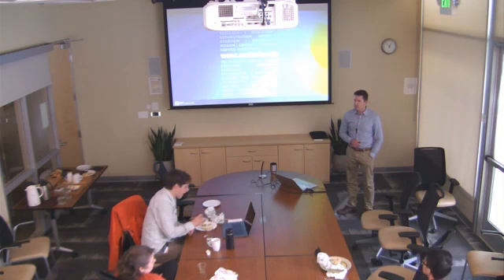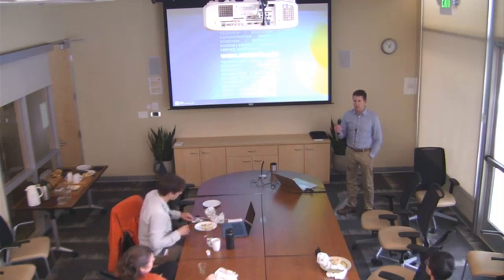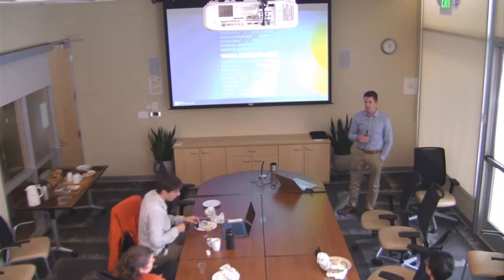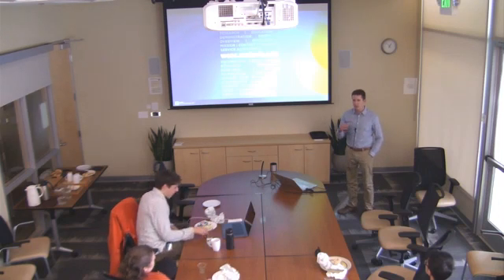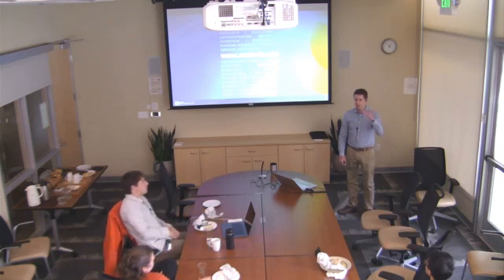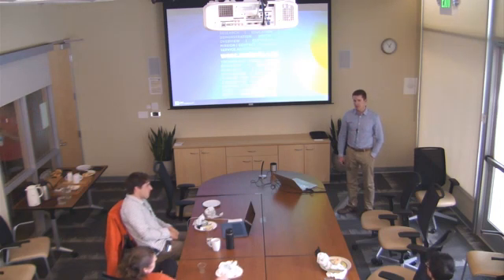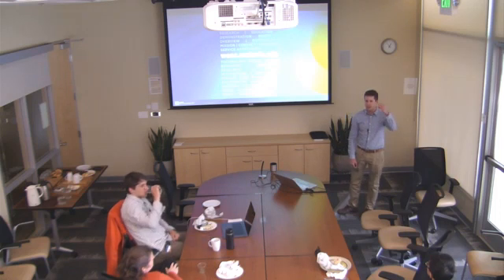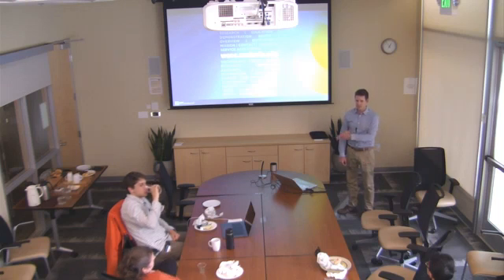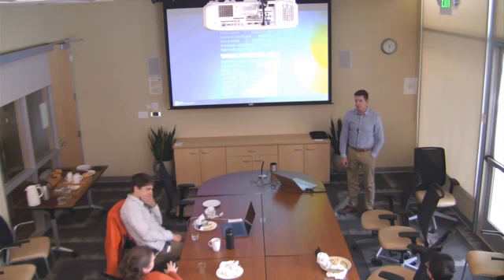People do zoning, even with single-speed equipment. One of our affiliates, Velara, formerly Butler, did all of these homes in Sacramento, and they include zoning in every one of their homes. For top floor and bottom floor, there's a pretty significant temperature difference between the two and load. So they generally install 2 zones in that scenario. And now they're doing townhouses where they have 3 zones with a single-speed equipment. And they have to get pretty fancy with the ductwork design. But as far as controls, it's fairly simple. You have a thermostat upstairs. It calls for cooling, and it asks the equipment to turn on, and the damper opens. But there's not a consideration for temperature in the attic or things like that.